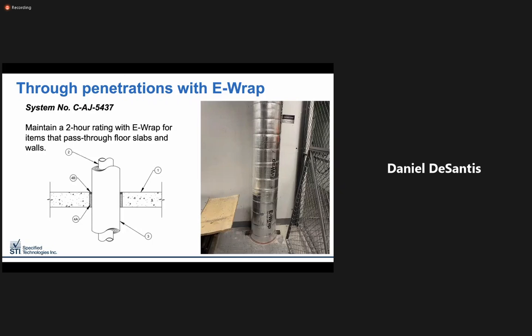To maintain the rating of a conduit or fuel oil line through an opening in a cast-in-place floor or a CMU wall, CAJ 5437 was designed to accommodate through penetration fire stopping of wrapped pipe and conduit. It's a simple LCI and mineral wool solution to maintain the integrity of your rated barriers when using E-Wrap.